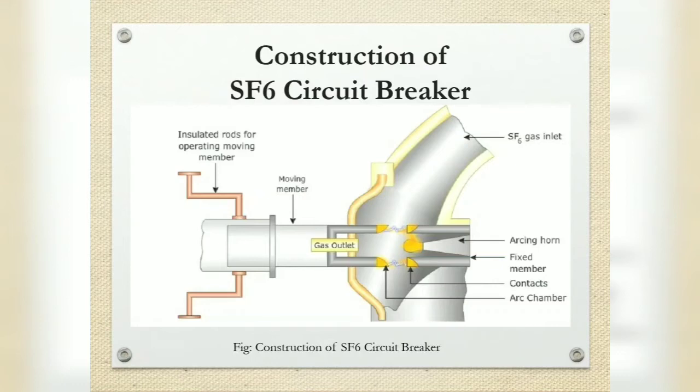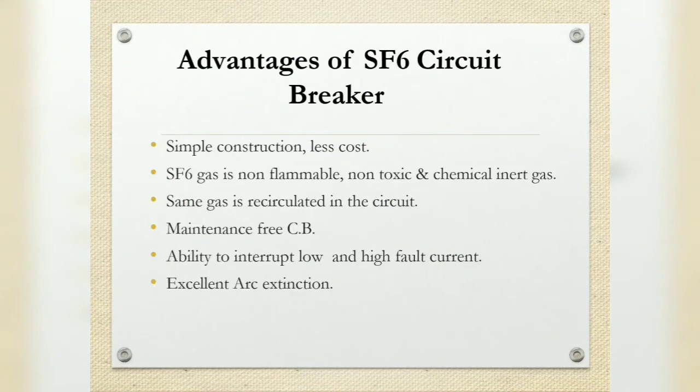Nowadays, a puffer piston is used for generating arc quenching pressure during an opening operation by means of a piston attached to the moving contact.